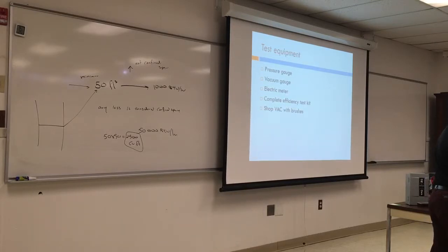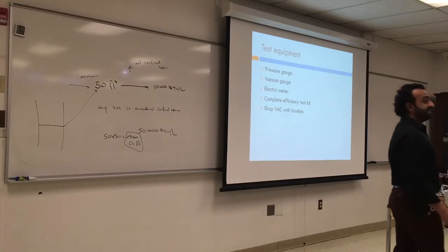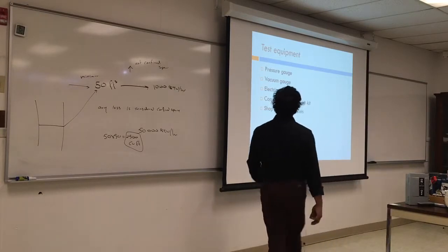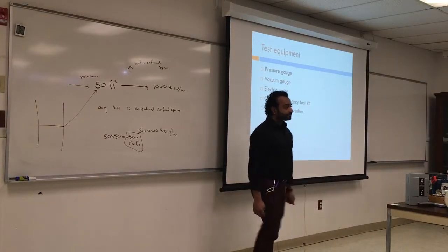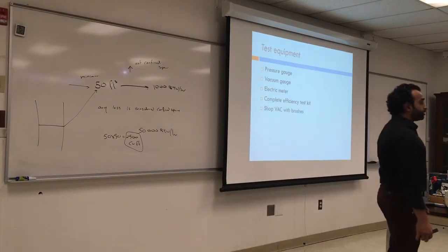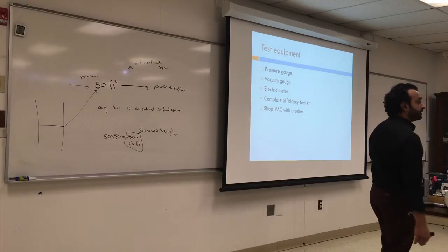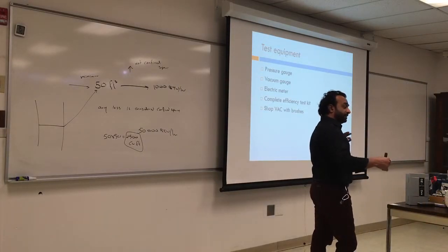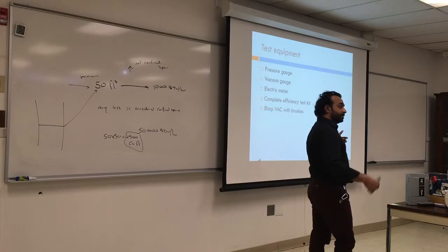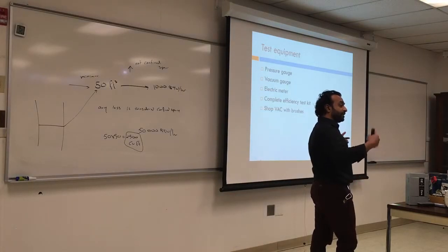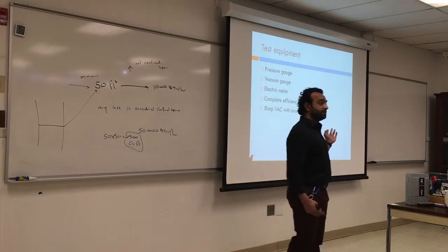And what should it indicate? How many psi? 100, 150. And you turn off the pump and it should drop by 15 to 20% and stay there. That's a good way to test the pump. Also, if it keeps dropping after you turn it off, it means there's a leak in the system. It should drop and stop. If it keeps dropping, something's wrong with the system, there's a leak.